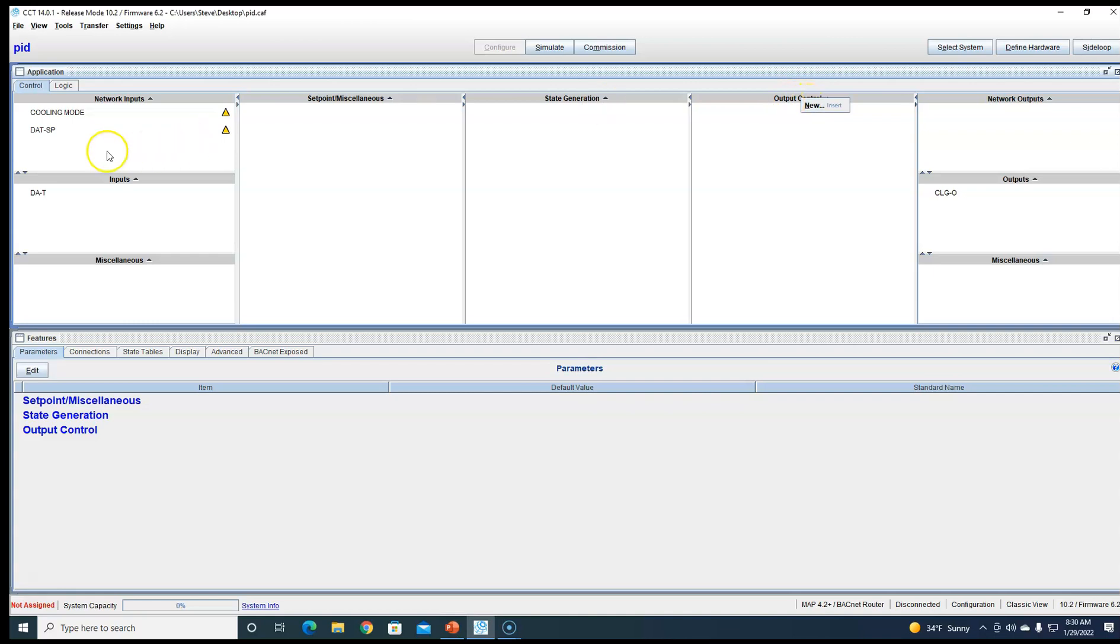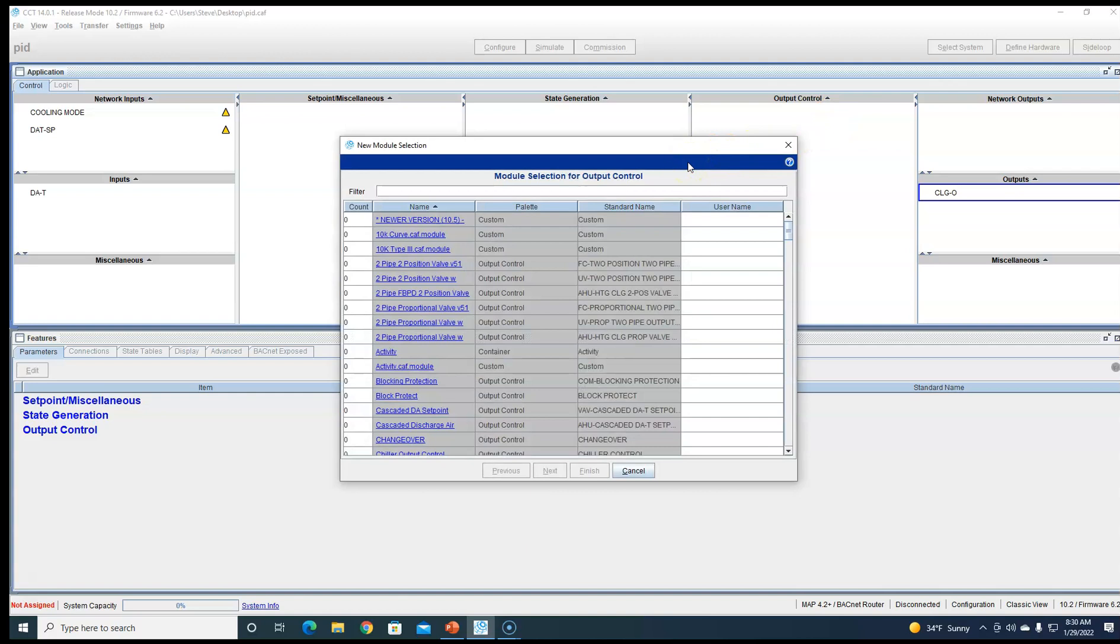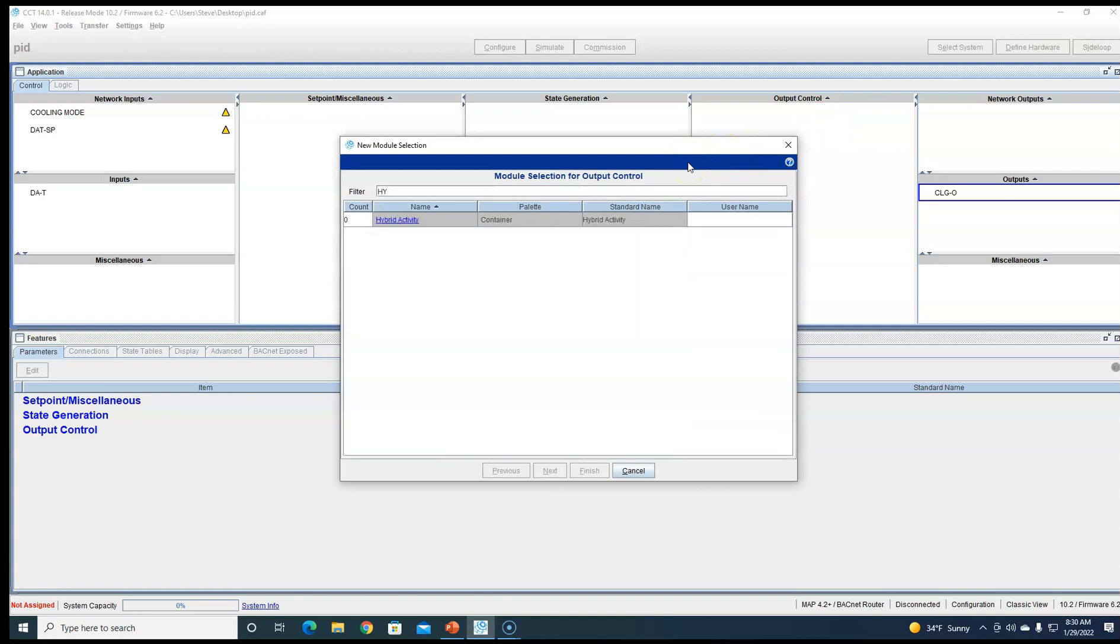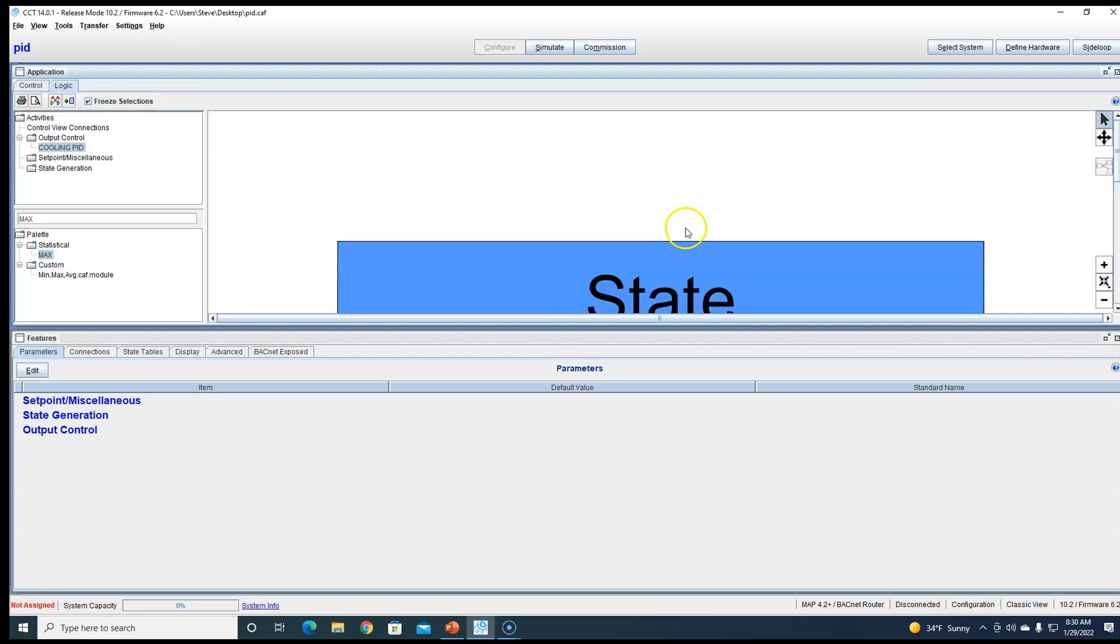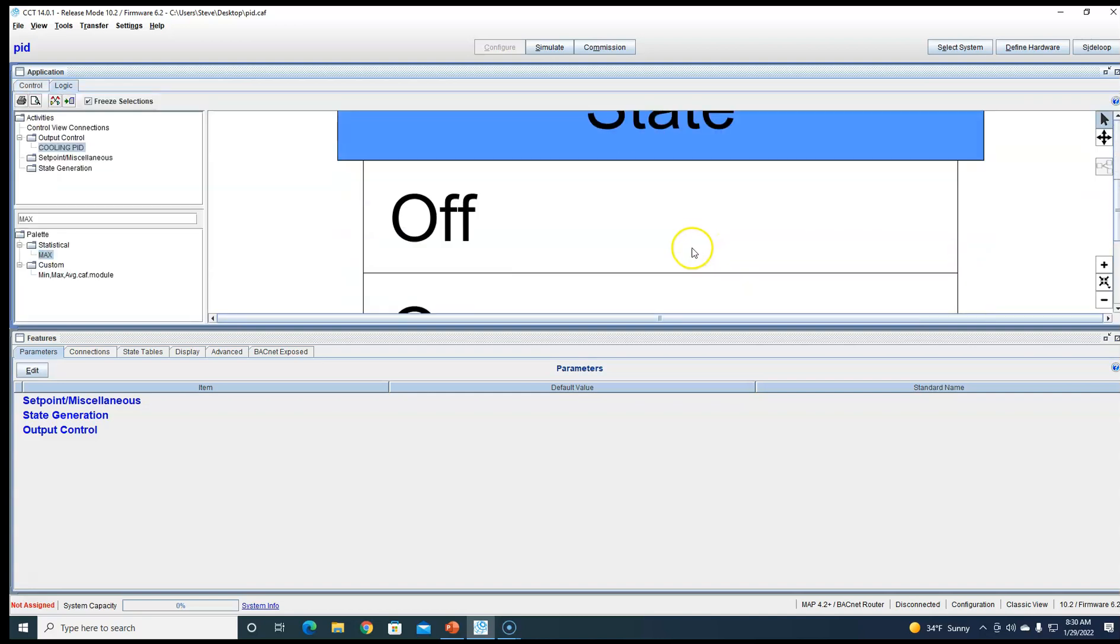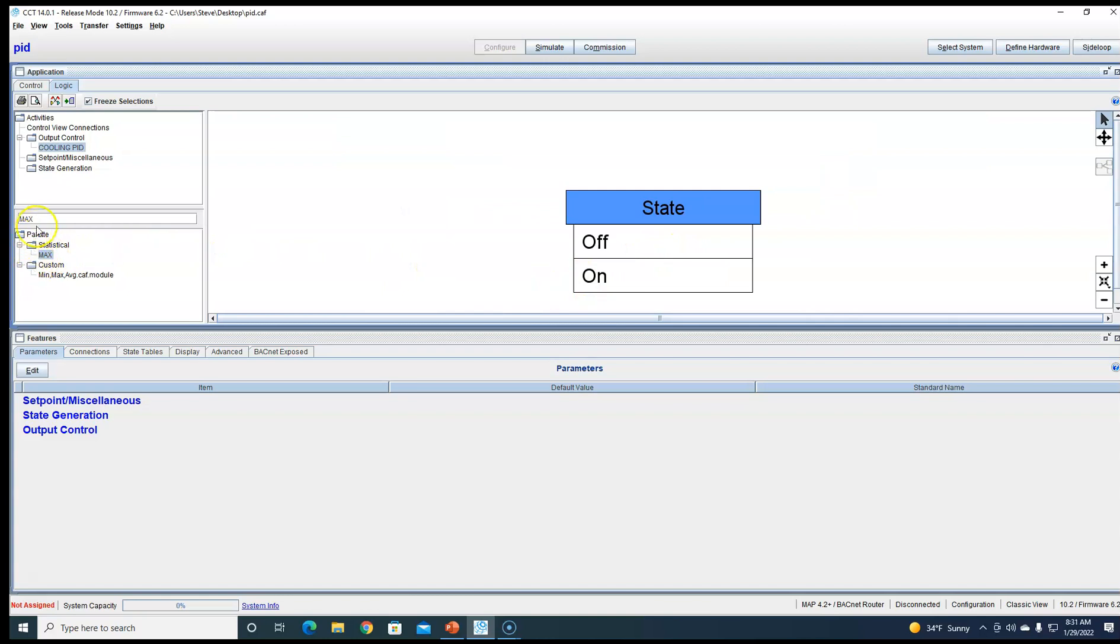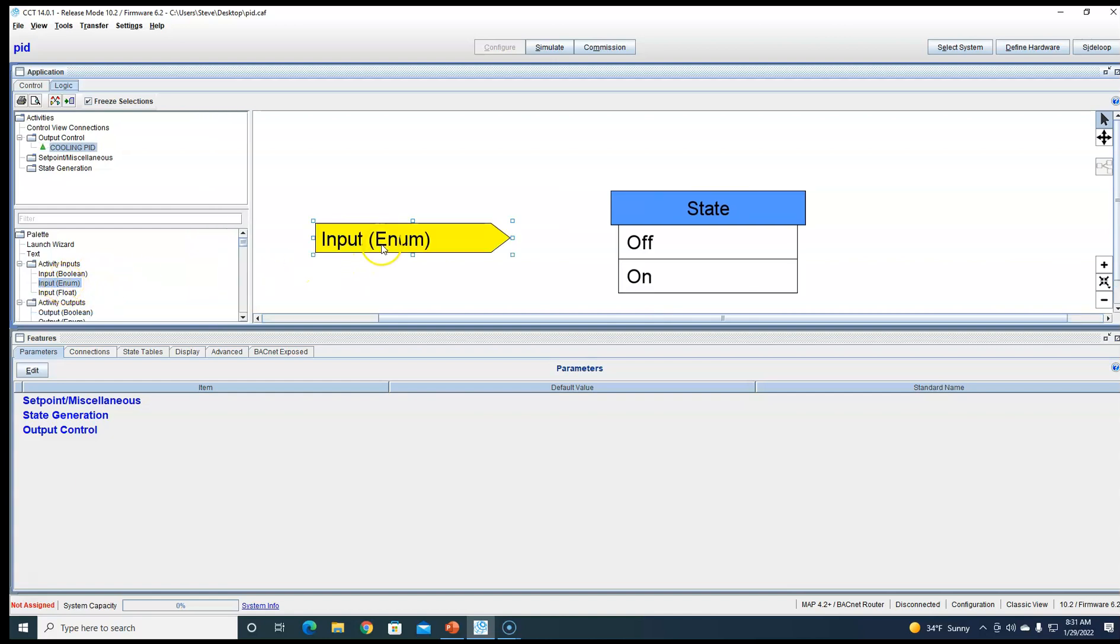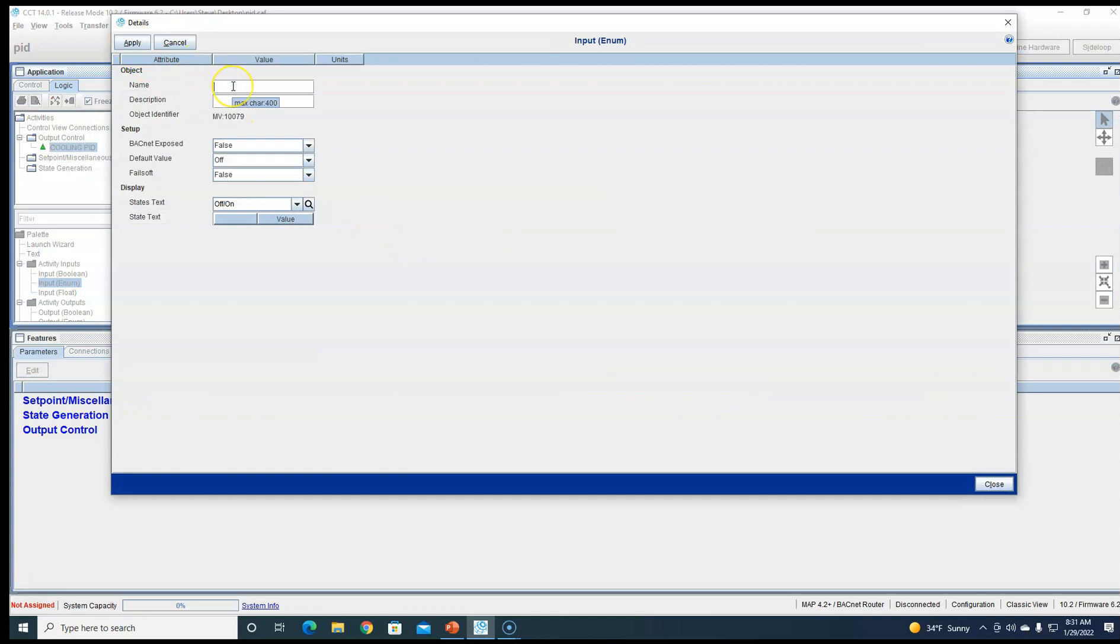We're going to make a mode, a set point, and a process variable over here and an output. Anytime you're going to do a PID, you have to do a hybrid activity. That's the only way to turn the PID on and off. So create a PID. We're going to go into view logic. First thing we're going to do is bring in an enumerated input over here, call it mode.